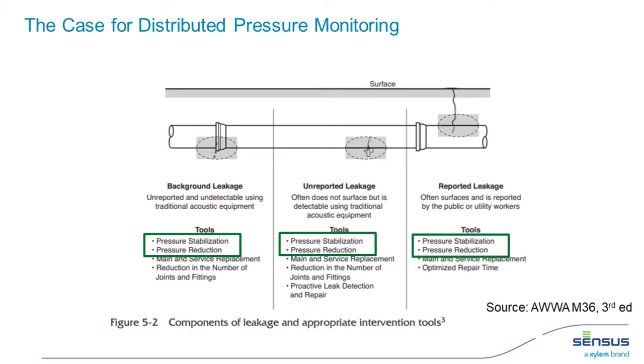When you're looking at distributed pressure monitoring on the surface here, all of it starts with pressure stabilization and pressure reduction, whether it's background leakage inherent to the system, an unreported leak that's cracked in there, or something that's made it up to the surface that you can see in the system. The lowest cost and first step to all of this is reducing the pressure and stabilizing your pressure.